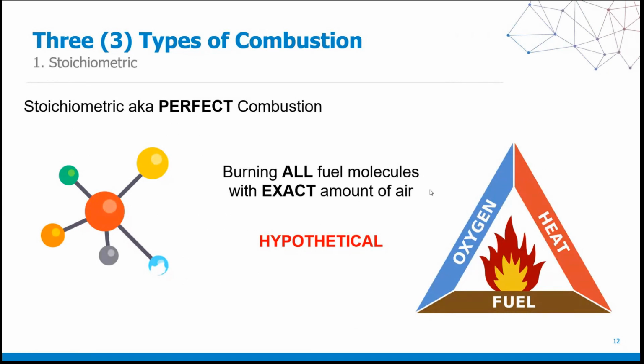And that is one of the numbers that you see when you first turn on a combustion analyzer. Outside in fresh air, you'll see that it says 20.9%. So since stoichiometric assumes we have 100%, we're already at a disadvantage. The other reason why we cannot have perfect combustion, and it's a secondary reason, but almost as important, is that we have thermal loss in any combustion process. And stoichiometric assumes that we don't have any thermal loss or heat loss. Since we do, again, we cannot have perfect combustion. So we're left with two other types of combustion.